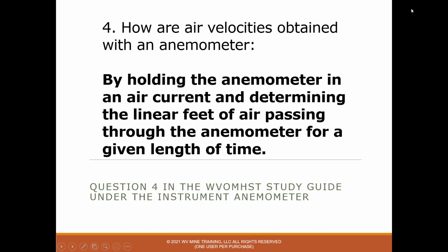Question 4, how are air velocities obtained with an anemometer? The answer is by holding the anemometer in an air current and determining the linear feet of air passing through the anemometer for a given length of time. The air flowing through turns the blades on the anemometer, and that records on the dials the linear feet of air moving, and we always do that for 1 minute.